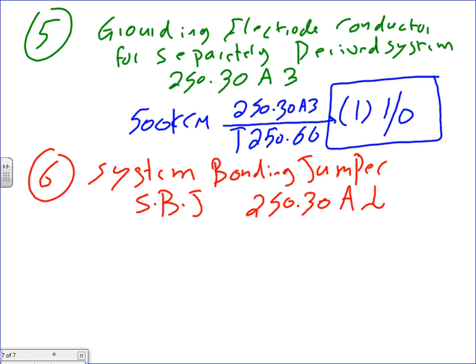If you have your own, this is my main, it's bonded. I moved in here and had a new transformer to take the 480 into 208. Right at the guts of the transformer, I tie the neutral to the ground, so I established my own neutral. That's called the system bonding jumper. This transformer I own, I operate, I maintain. Piece of cake. It is sized the same way, guys.